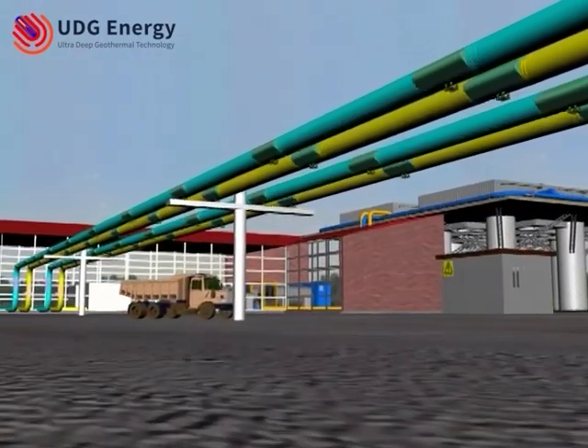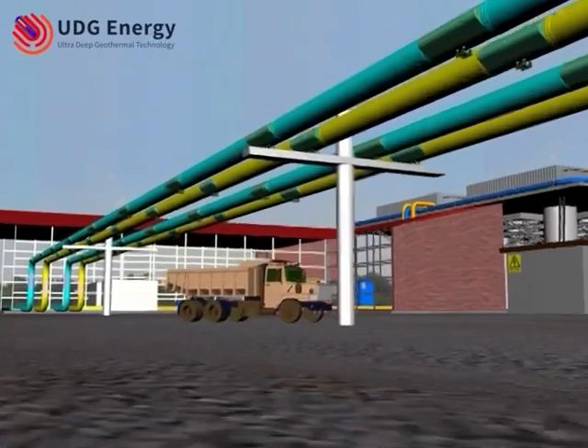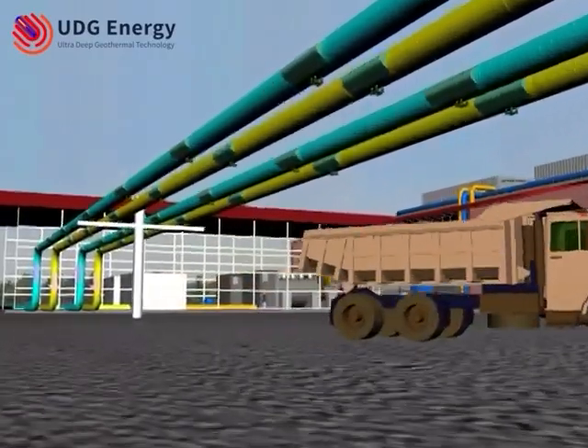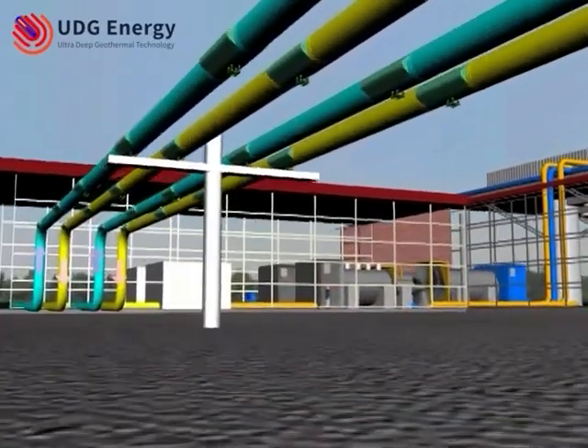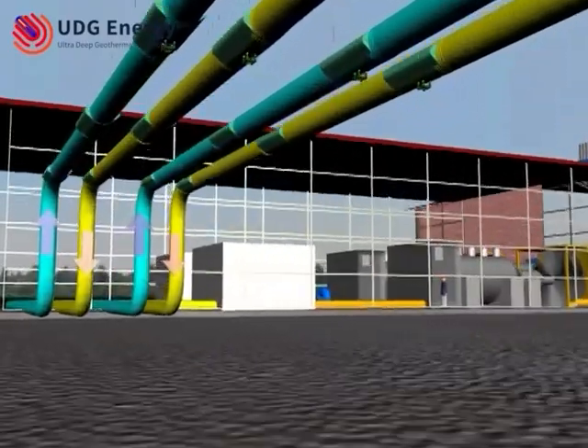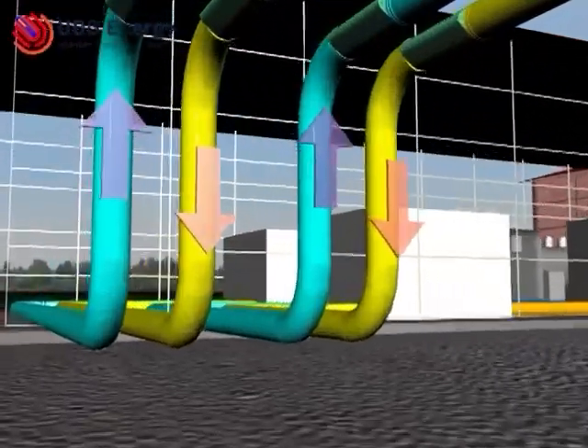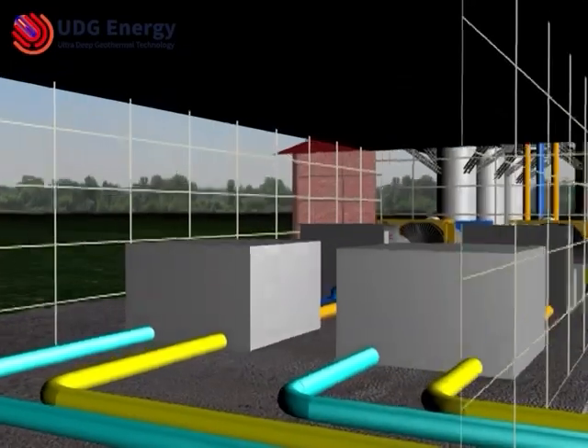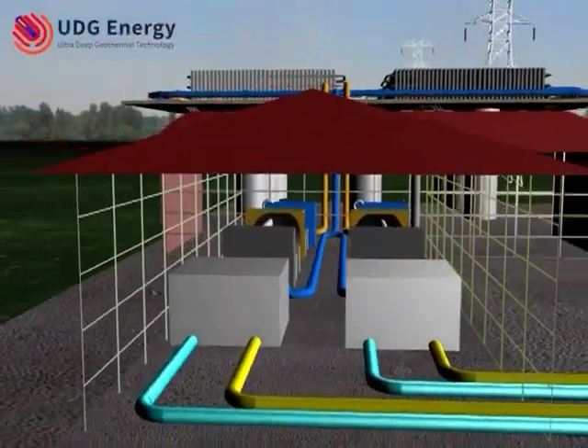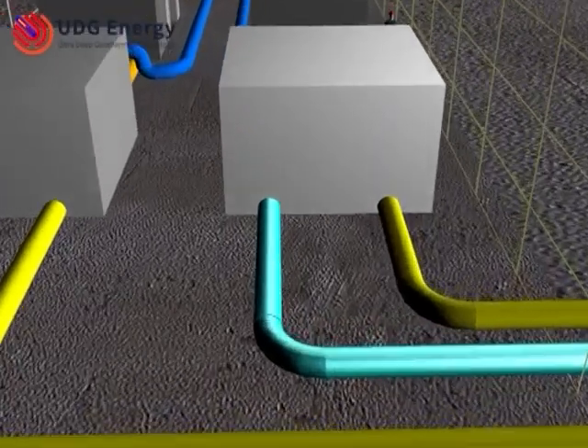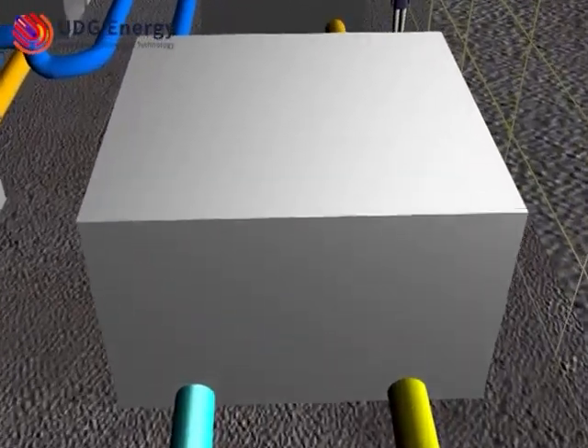The working fluid from the primary production circuit is led back at approximately 90 Celsius degrees to the underground system. The now heated working fluid of the second closed circuit is used to power the steam turbines that generate emission-free electricity. The green electricity is put on the grid through the transformers, and the working fluid of circuit 2 at that moment is still 160 Celsius degrees.